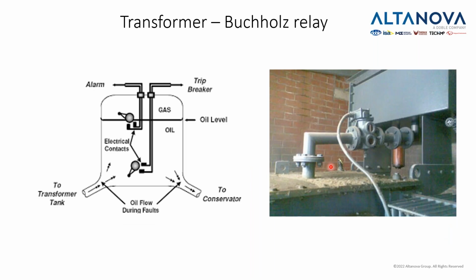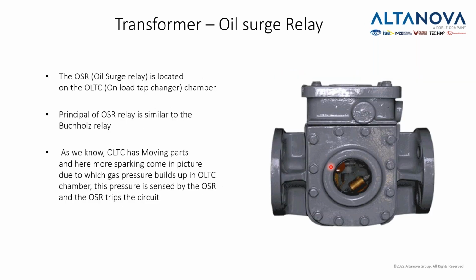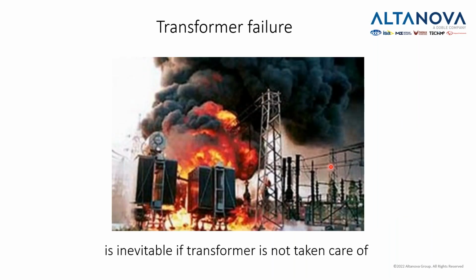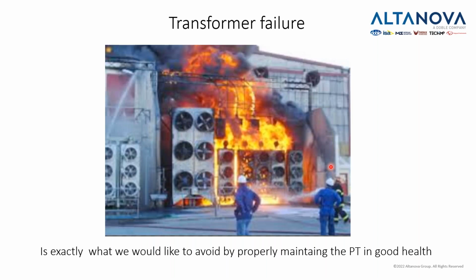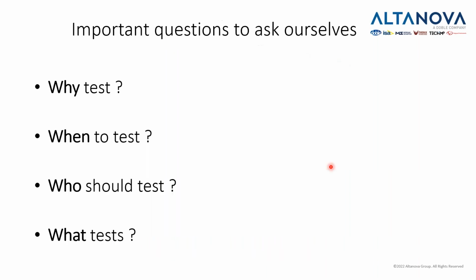Here we have a more detailed design presenting the Buchholz relays, which I'm sure you'll have time to check later. And we have also an oil surge relay, an additional element to protect the transformer from failure. Talking about failure, that is something inevitable if the transformer is not taken care of. And it is exactly what we would like to avoid by properly maintaining the power transformer in good health.